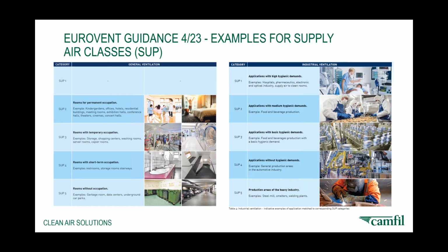SUP2, for instance, in general ventilation will be kindergartens, offices, or any area that's going to be permanently occupied with people. And the same inside in an industrial ventilation or a plant with industrial ventilation, SUP2 would be again applications with medium hygienic demands. So there's a difference between the general and the industrial ventilation classes. But the guidance given for filtration efficiencies comes from looking at the ODA, or the outdoor air quality, so the area that you're based in, and then the type of filter you would use to create an SUP1 or an SUP2, etc., type of indoor location.